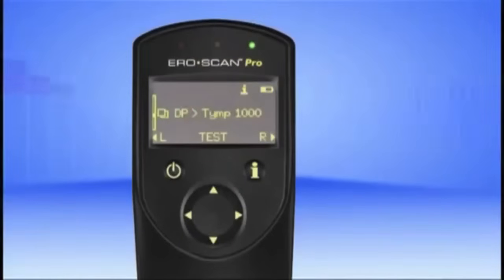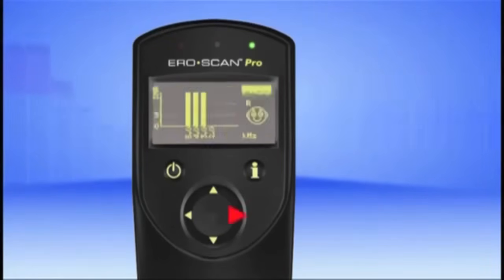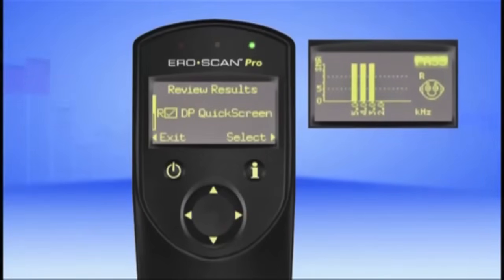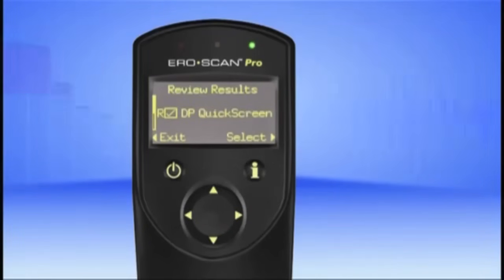Now that we've covered testing, let's move on to reviewing and managing the results. To review any previous test results, use the navigator and scroll down the main menu options until Show Results is visible. Pressing the right arrow on the navigator will select it. This will then bring up the Review Results selection. Pressing the right arrow on the navigator once again will select it. Here, you'll see all tests saved in the instrument.